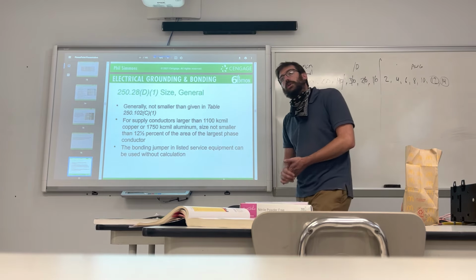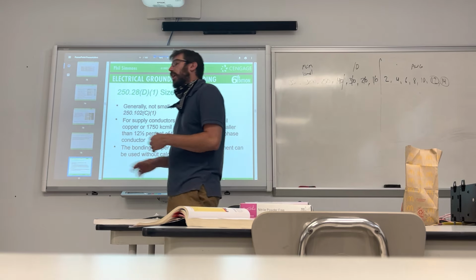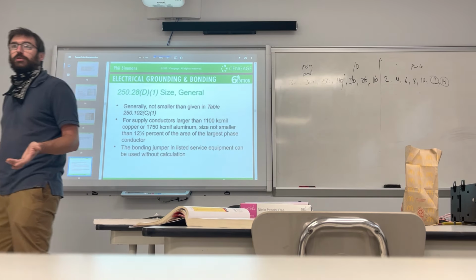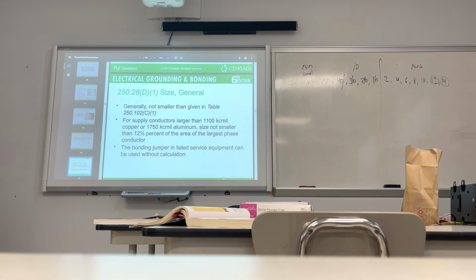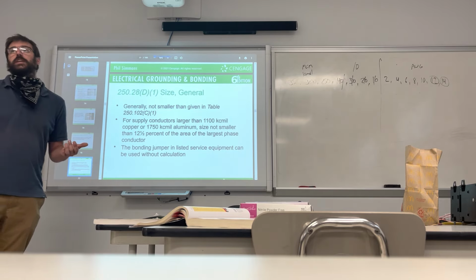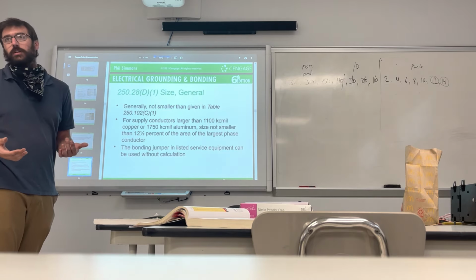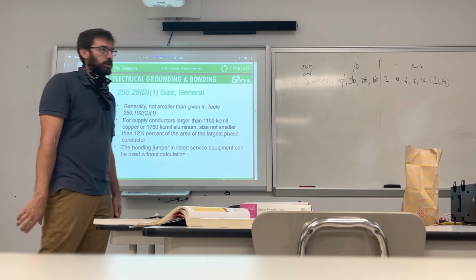So when you're doing your grounding, just make sure, I know solder is 9/10 of the law anywhere else. Like if you do a solder connection in a car, reliable. You do a solder connection in a motor control board, reliable. But as a ground, it's just a liability. Grounds, it's best to be mechanical or via weld, but the caveat with the weld is the material has to melt at the same temperature or higher than the wire itself. Solder will be much less.